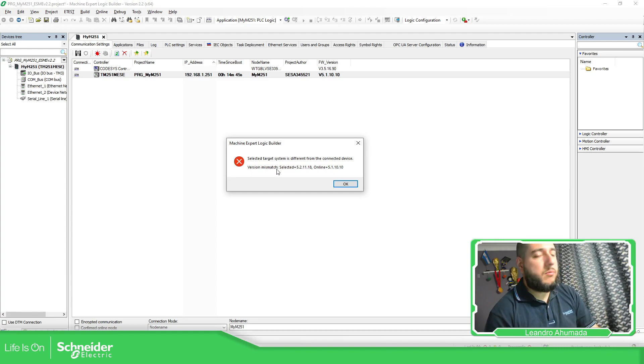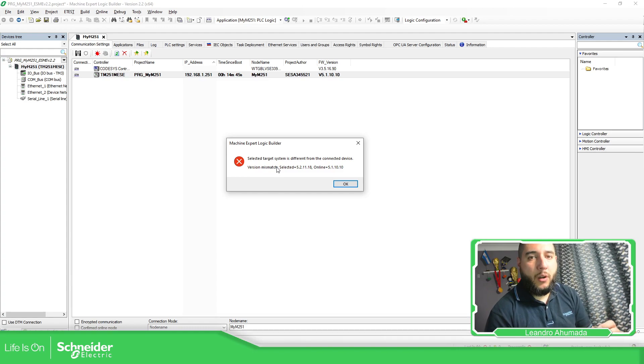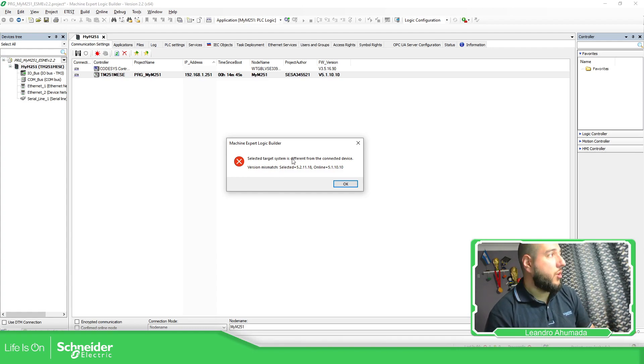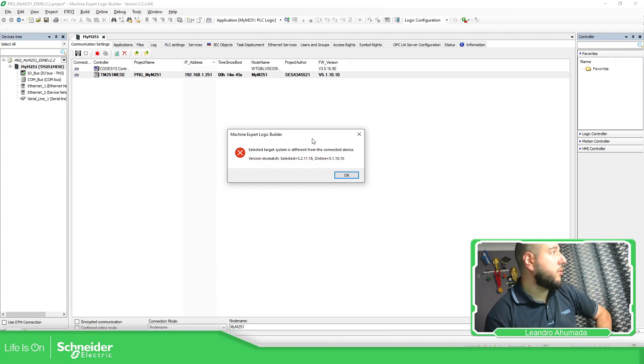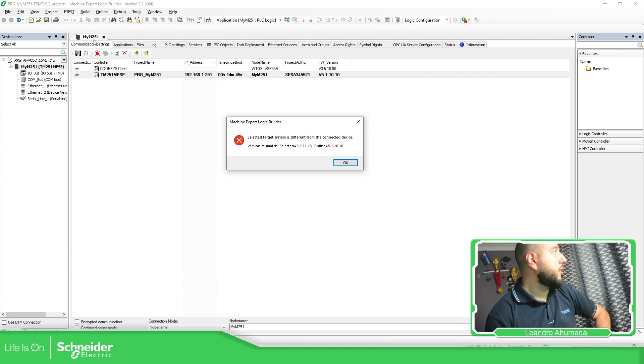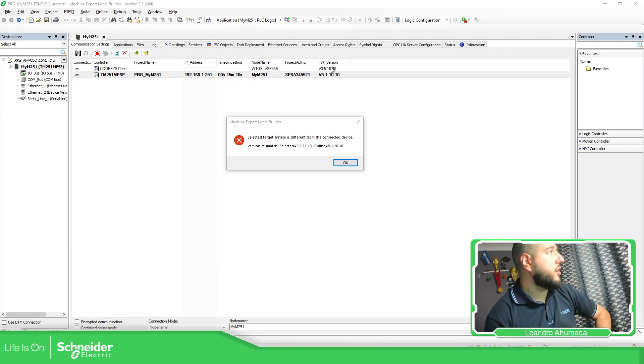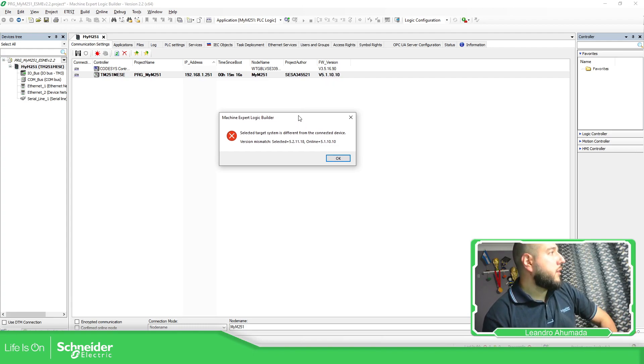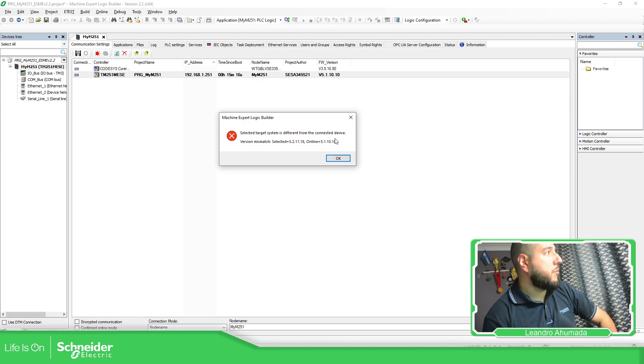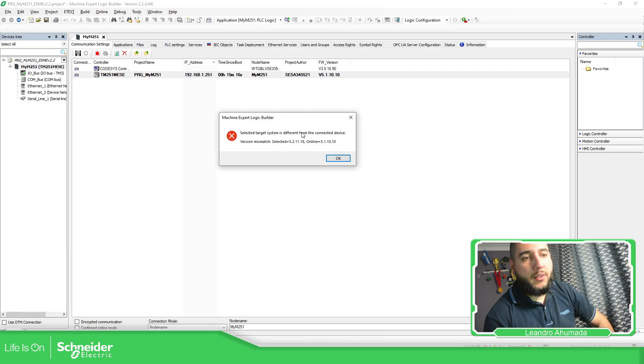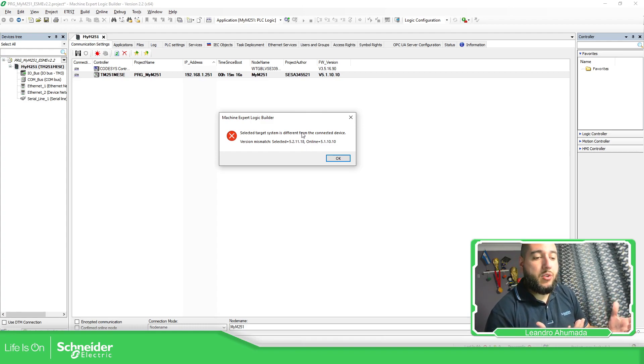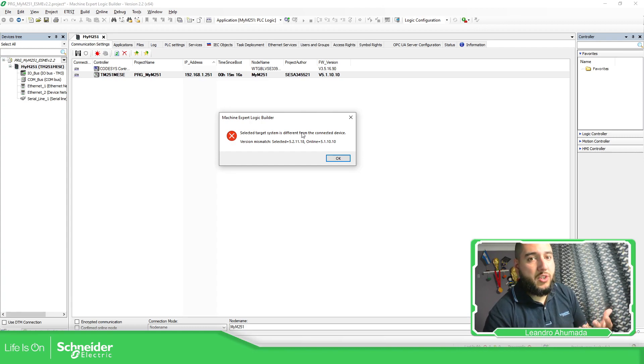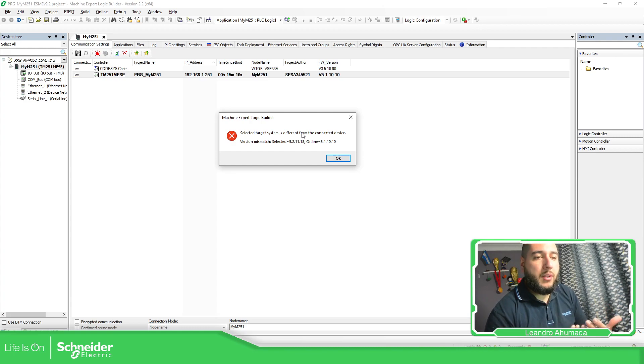The version mismatch is related to the firmware on the PLC. So if you take a look over here in the communication settings, you can see here the firmware version. This is the firmware of the PLC they are trying to connect to. So it says online it has this firmware version. Now the selected is this firmware version and it means that probably you're using a version of EcoStruxure Machine Expert different to the one that is on the controller.